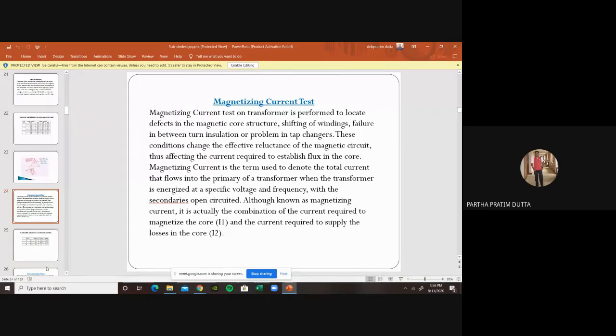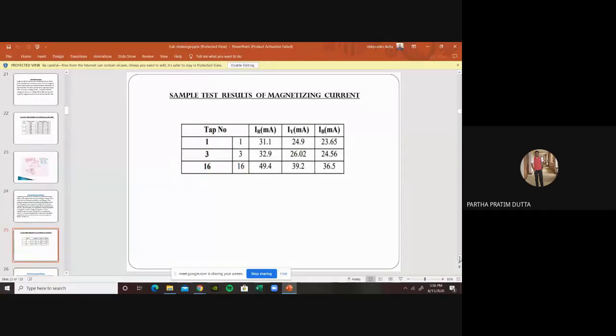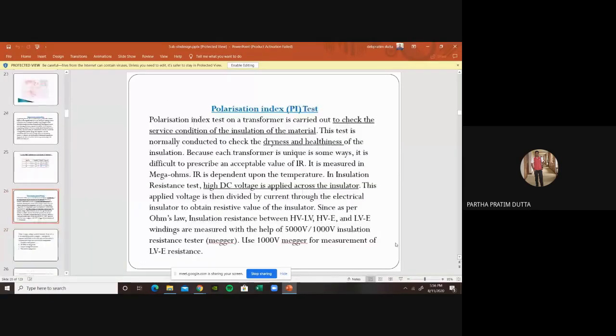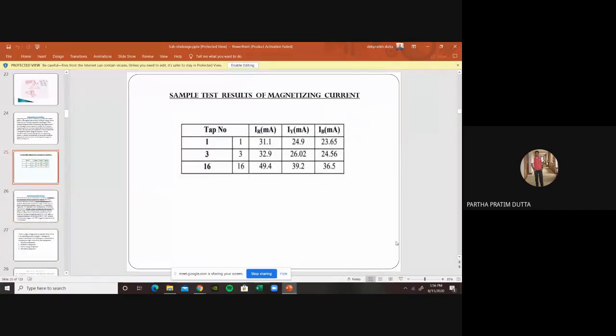we use a meter to measure the total power, that is the total loss, and usually we focus on the magnetizing current, and that usually comes for the new transformer. It is coming 6 to 10 milliampere, but in that particular case you see the IR, IY and IB going to 30 milliampere for different tap positions. Why is it happening? Because it is a very old transformer. For a new transformer, we experience that 6 to 10 milliampere is usually the magnetizing current.